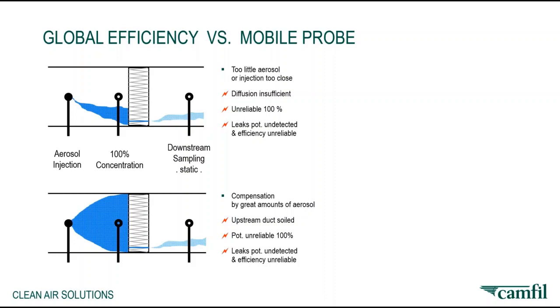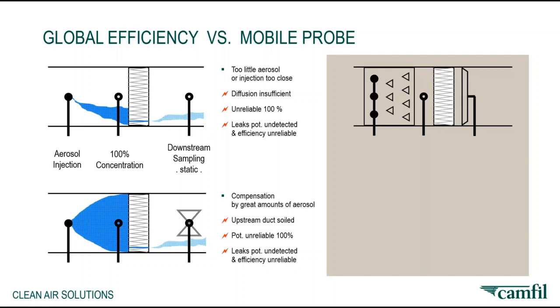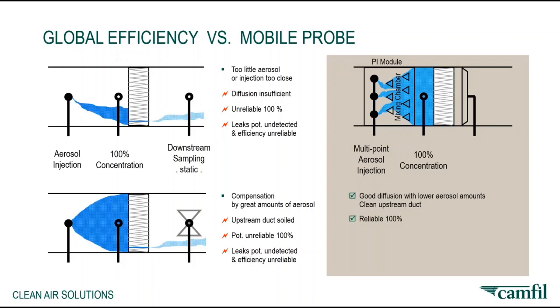In contrast, this would be the situation when you use a mobile probe and an injection module. In this module, you get a multi-point injection and, well, let's call it a mixing chamber. This module ensures you get a good diffusion with lower aerosol amounts and a clean upstream duct. And by extension, your 100% measurement will be reliable. And now that we have a mobile probe, we get to sample the full airstream section, not at one time, but progressively. But yes, you will also get a reliable efficiency and a reliable leak detection, even an approximate leak location in optimum cases. We would actually like to know your opinion on that.